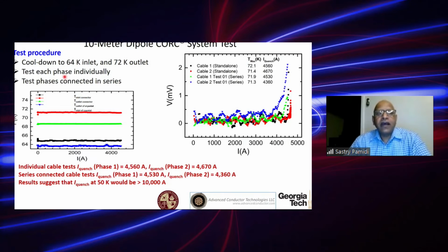You can see here the critical current. We cooled each pole of the dipole, and each carried close to 5 kiloamps. So that means if we use both cables as one system, one cable, we could go up to 10 kiloamps. It is not only carrying current, but if you see the temperature, when we went to about 4.5 kiloamps, the temperature of the gas is around 65 or 68, between 65 and 70 Kelvin. That means this cable, if I go to 50 Kelvin, would carry about 10 kiloamps each pole. So it would be a 10 kiloamp dipole.